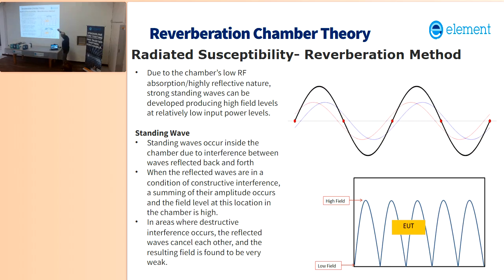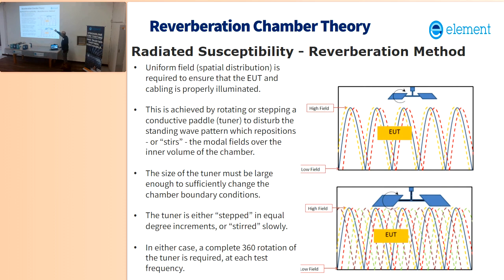So we put our test unit, our EUT, in there. And if we didn't turn the stirrer, we'd just have peaks that happen in one place and nulls that happen in another place. But we rotate the stirrer, rotate the tuner, either in steps, defined increments, 10 degrees, 30 degrees, something like that, or you stir it slowly, continuous rotation. And there are different requirements: MIL-STD-461 is only stepped. You have to step it, discrete steps. DO-160G, DO-160H is a continuous rotation of the tuner.